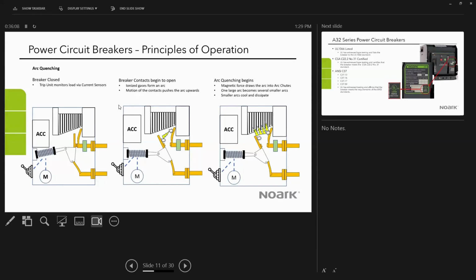The motion of the contacts and the shape of the contacts begins to push that arc upward toward the arc chutes, which are the lines that you see up at the top. And then as the arc approaches the arc chutes, it generates magnetic forces that draw the arc into the arc chutes, and it breaks the arc up into many smaller arcs. Then they have an opportunity to cool and dissipate.